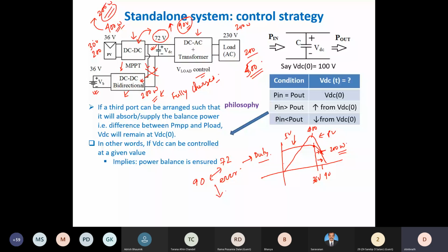After that, it cannot cater to the load demand, so this extra power will start coming from the capacitor's stored energy, and the capacitor voltage will now start falling. As soon as it falls below, say, 50 volt — a lower margin — you know there is a power balance problem, that solar power is less than what is required by the load. So you now start discharging the battery.